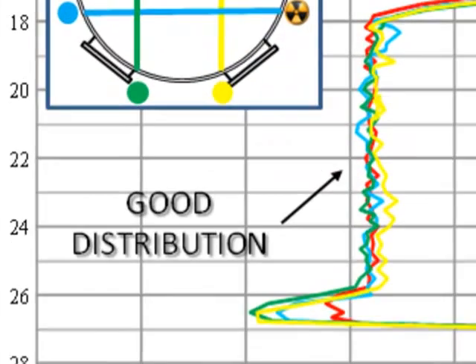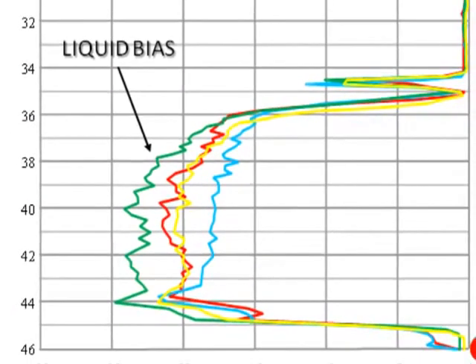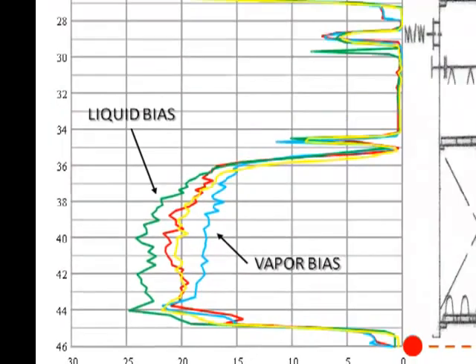So, the upper packed bed showed good distribution, but the lower bed showed poor distribution, with a liquid bias on the green scan and a vapor bias on the blue one.